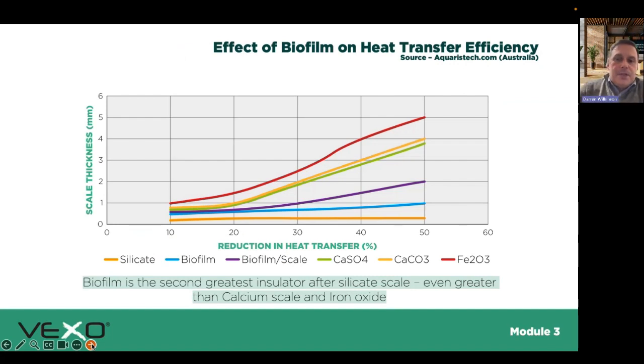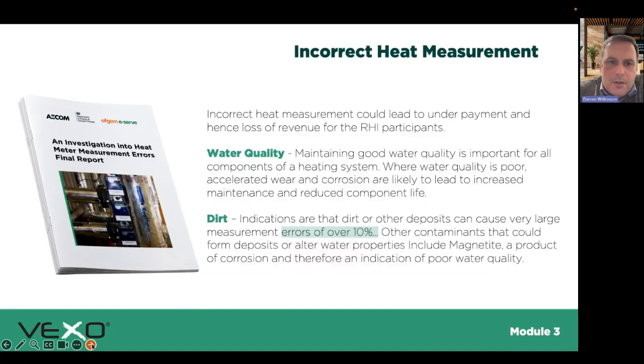But getting back to biofilm, scale is a thermal insulator. If we get scale on our boiler, it's going to be putting more gas in, or more energy in, to meet the same level of demand of energy going out. And actually, biofilm is a greater thermal insulator. So having biofilm on our evaporator coils in a chiller, or even the condenser, or even in a boiler and in our radiators, the bacteria biofilm can create significant loss of energy, particularly where we have a lot of HIUs, heat interface units, that are being installed.